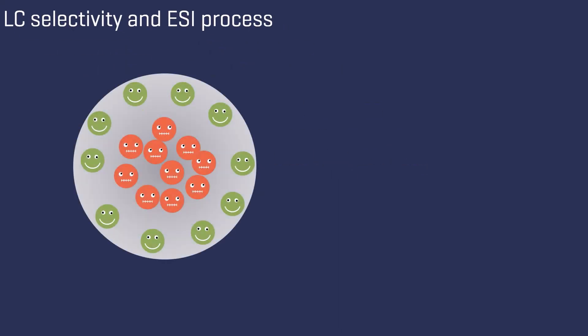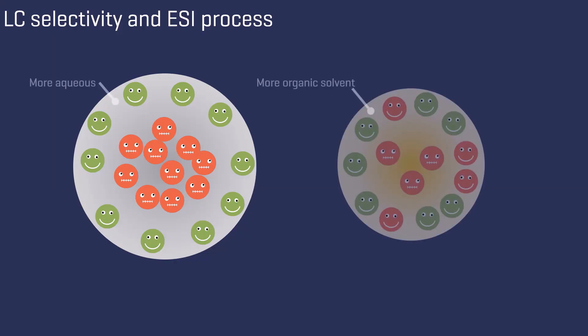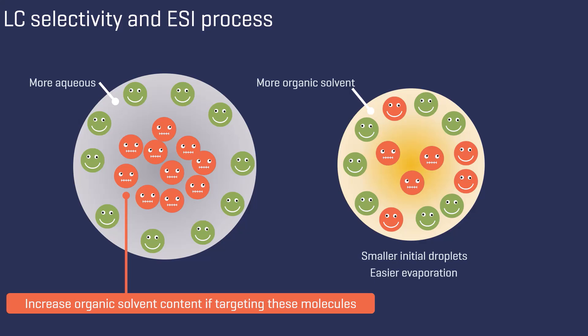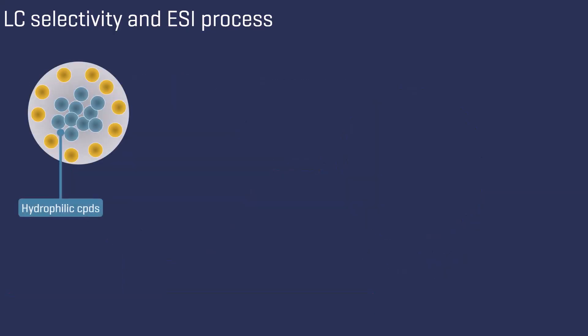The likelihood of detecting specific molecules and their tendency to loss is influenced by their location within the electrospray droplets. This effect is especially pronounced when the droplets are primarily aqueous, because the initial size of droplets containing more organic solvent is smaller and evaporates more readily. If targeting molecules that are located at the center of aqueous droplets, it is therefore advisable to increase the organic solvent content. As described before, these are molecules that are more hydrophilic.